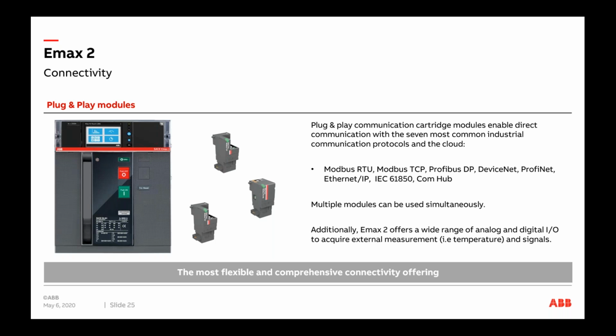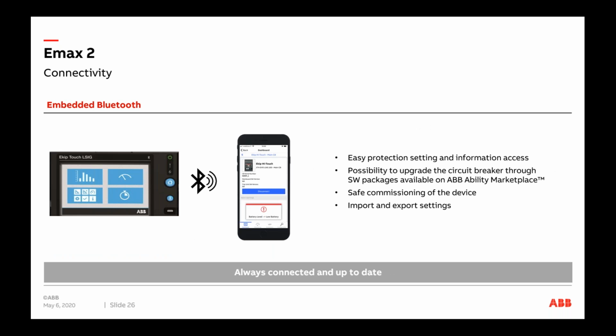So protocols like Modbus RTU, Modbus TCP, Profibus, and IEC 61850 are part of the Emax 2 accessories portfolio. Now, Bluetooth functionality is embedded in Emax. It's not necessary, and it's not on always. It can be enabled based on user or operator functionality.